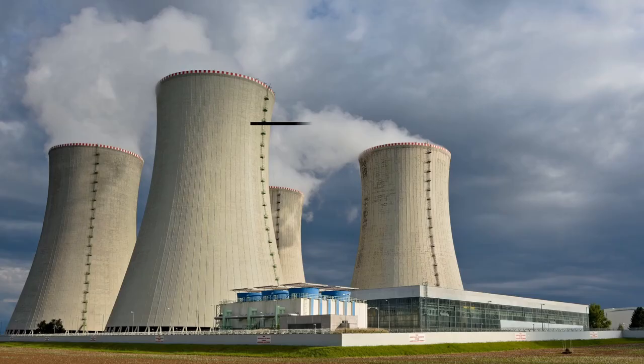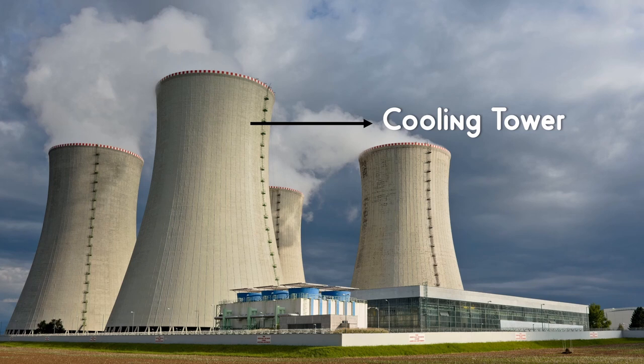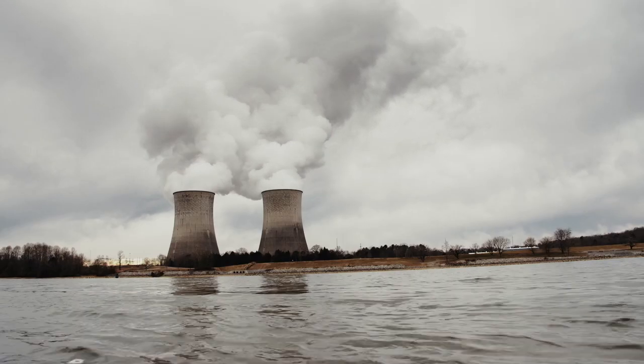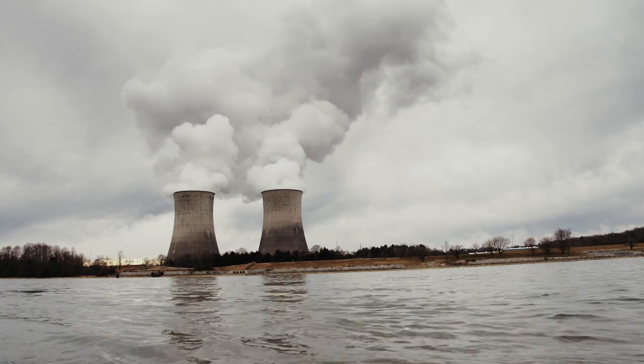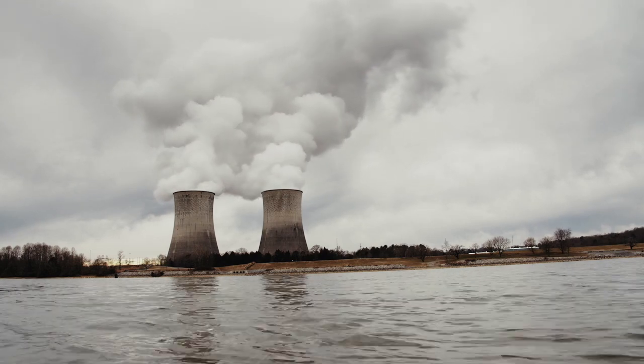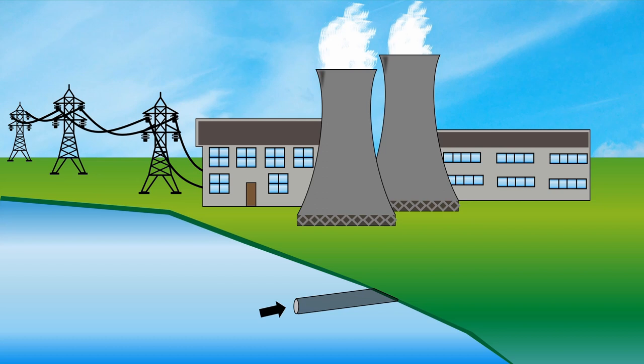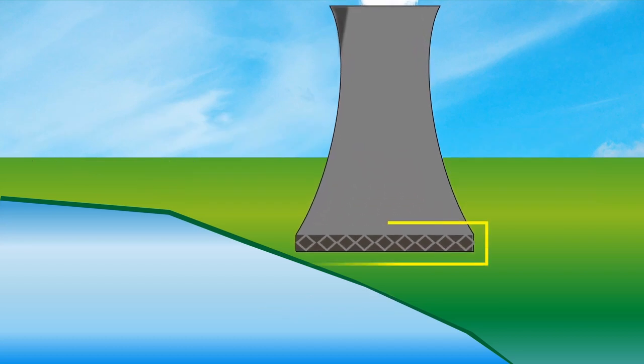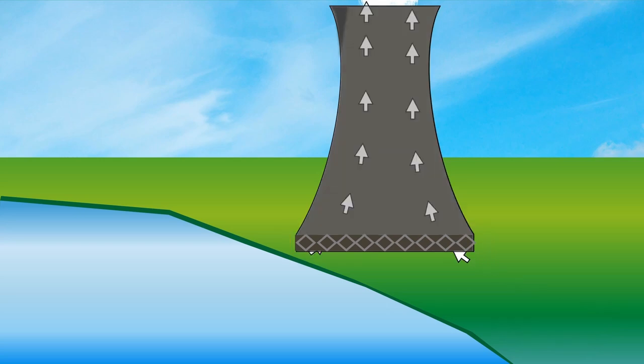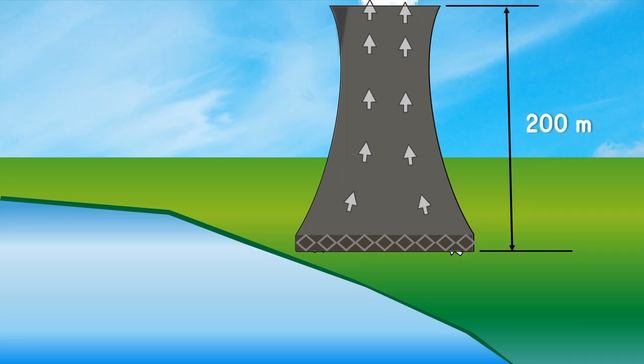This hyperbola shaped structure is the cooling tower. Do you know why hyperbola shape is preferred? First and foremost the hyperbola shape strengthens the entire structure. Constructing this shape requires fewer materials. At the bottom of the tower the structure is open to draw fresh air which then flows upwards. For sufficient air flow to occur the height of the cooling tower tends to be large around 200 meters tall.